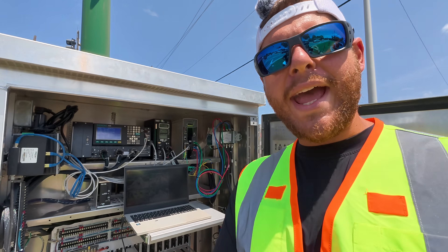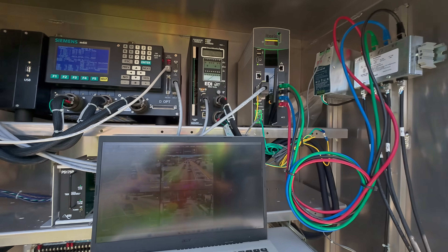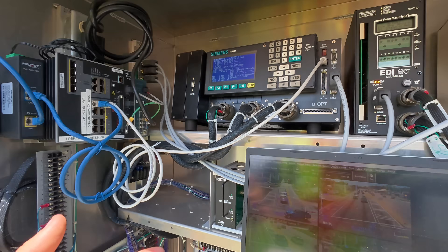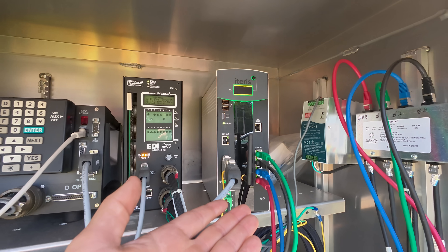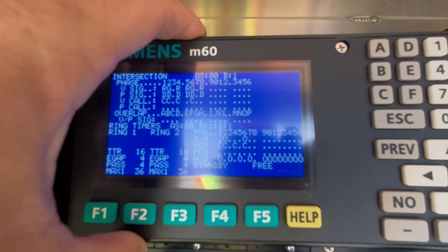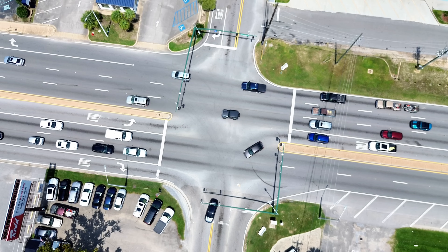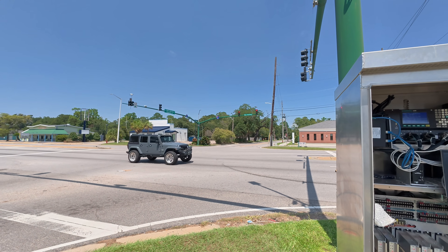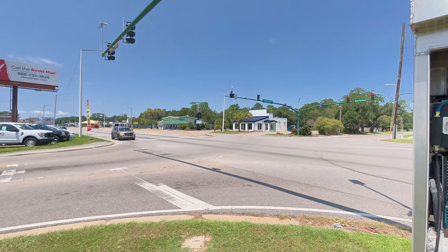Now that we have the cabinet open, I can show you how the cameras are working. These vehicles here sitting on this approach — which is going to be phase four — are getting detected by that camera. This CCU is going to recognize that and put in a call into the traffic signal controller cabinet. You can see they have a call for phase four, which is the straight or left-hand turn approach on this intersection, and they will soon get a green light.